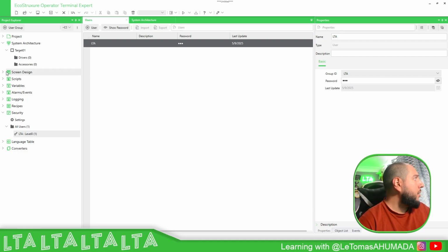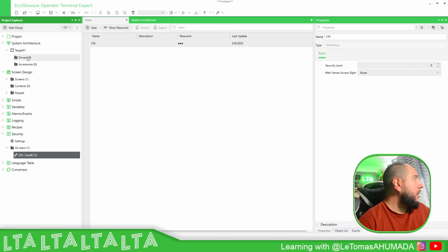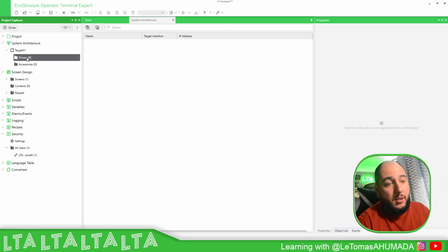So what we need to understand is that in your particular case, you probably have a PLC, and the PLC has the NTP or SNTP. So you will connect to a server, and the server will send the date and time. Then the PLC synchronizes, and then you can divide the different variables if it's in a structure and send that information to the HMI, and the HMI will try to update the date and time. That's one way, or you can manually adjust the date and time of the HMI.